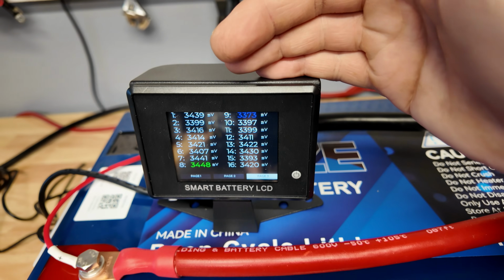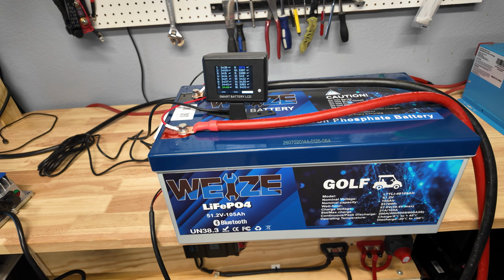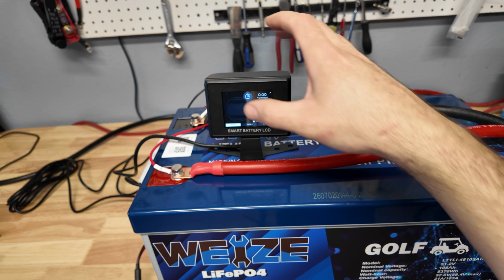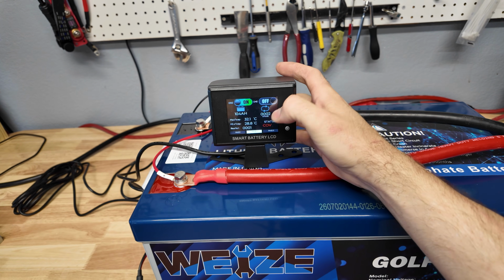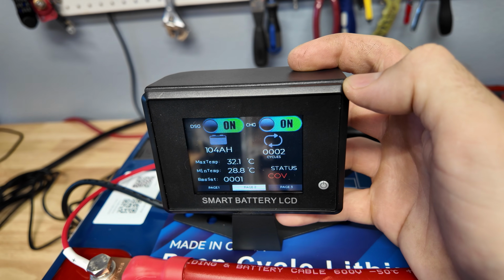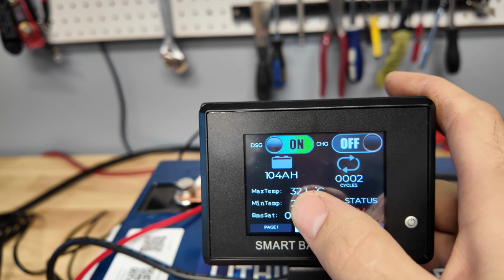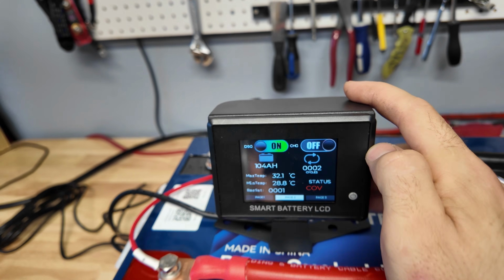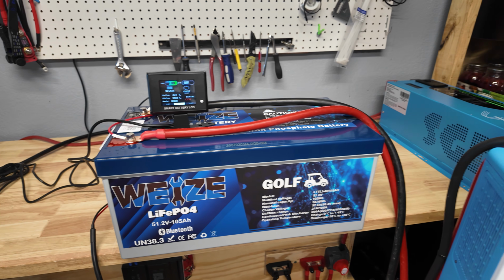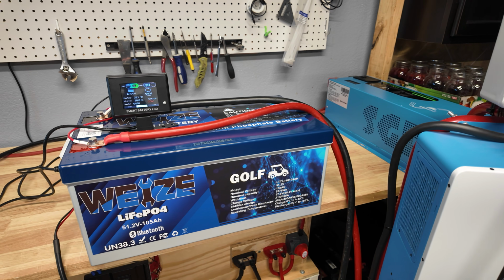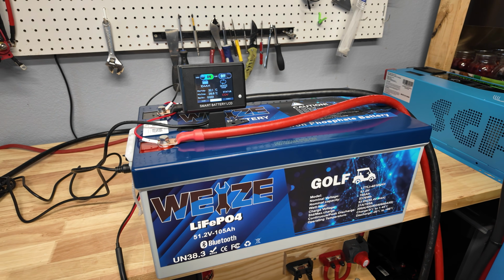If we could get these cells to 3.65 volts, we'd definitely be able to put more capacity into the battery, but I think this BMS is just limiting that for some reason. I can't even turn the charging rate back on, it just immediately goes off. Even the meter here is only displaying 104 amp hours. If that's the case, it's simply a BMS programming error that could easily be remedied. Hopefully the cells themselves are actually pretty good.